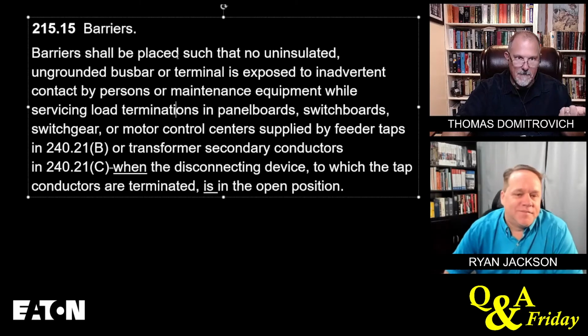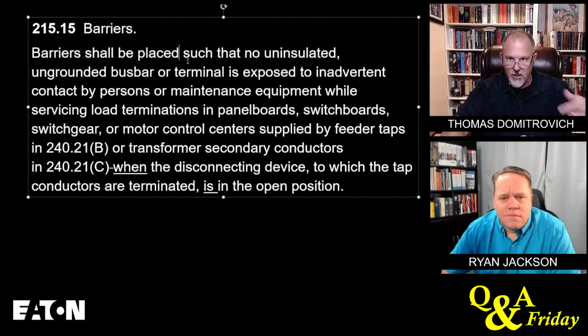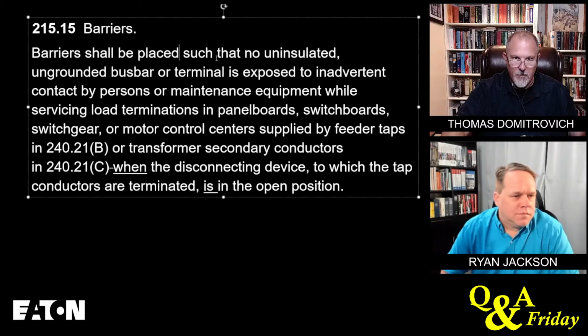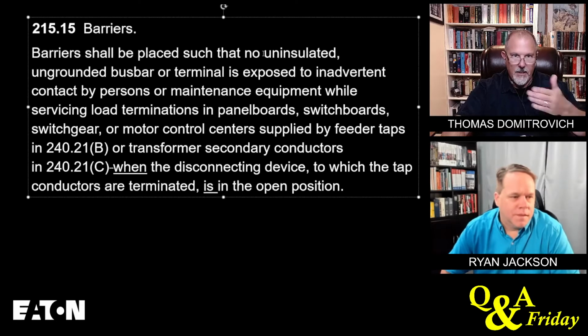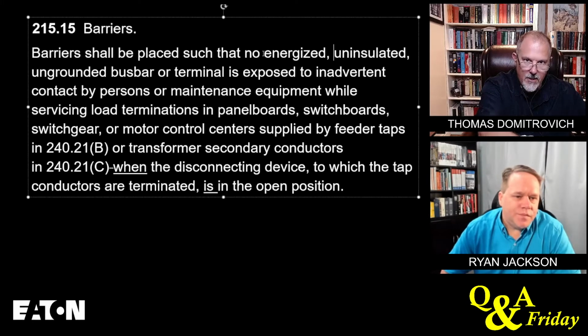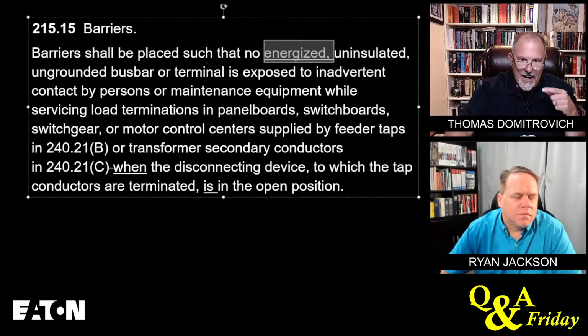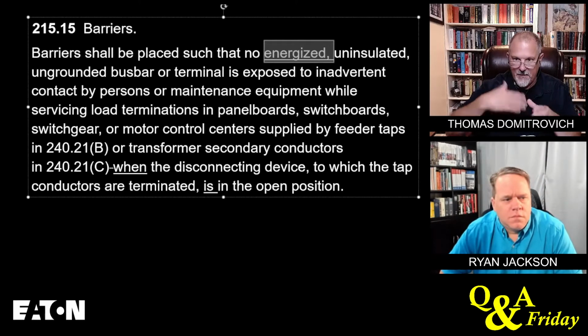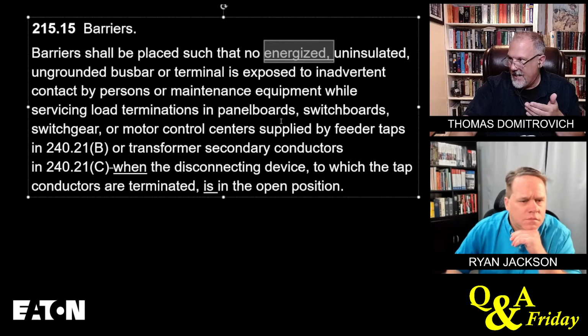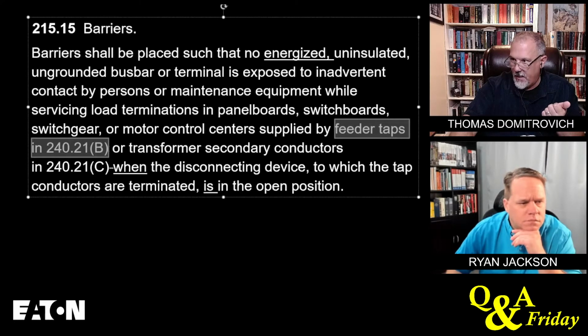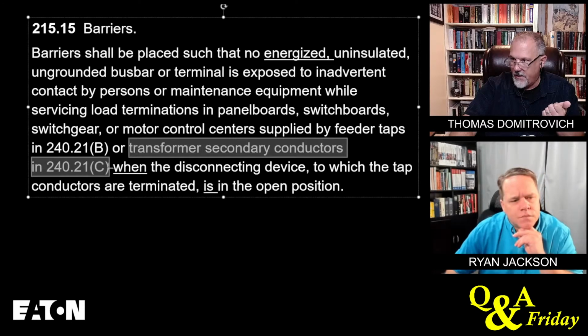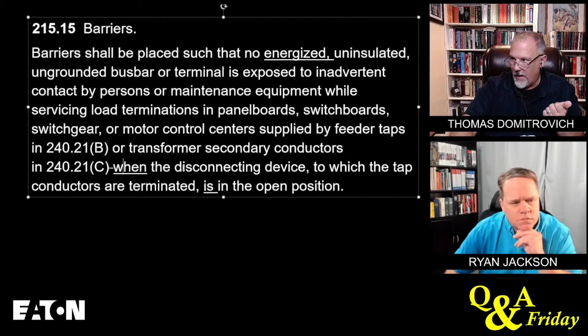So I had a TIA, which I think has only one dissenting vote on it so far, and I know it's been through the recirculation. So all I did was say barriers shall be placed such that no energized, uninsulated, ungrounded place. So we added energized, comma, right? I believe that's exactly where we put it. Now, when I was looking at this, while developing my TIA, I went down to here. Down here it says load terminations or motor control supplied by feeder taps in B or transformer secondary conductors in C.